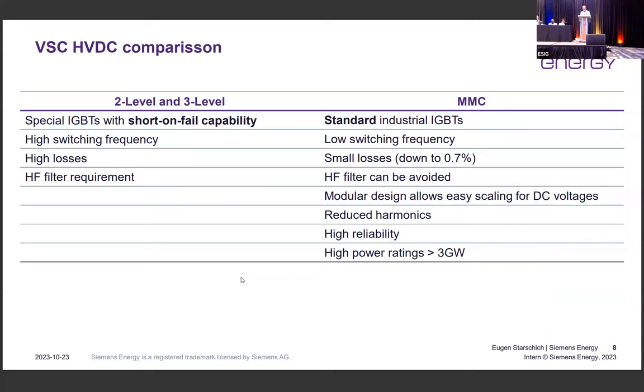So let's do a quick comparison of 2- and 3-level converters versus the MMC. As said before, special IGBTs with so-called short-on-fail capability are required, which is not the case for the MMC, where standard industrial IGBTs can be used. We have very high switching frequencies for the 2- and 3-level converters, while the MMC has very small switching frequencies. And this results in losses also. With 2- or 3-level converters we have very high losses, which are 1.4, 1.5%. In the MMC technology, we can go down to 0.7% converter losses.